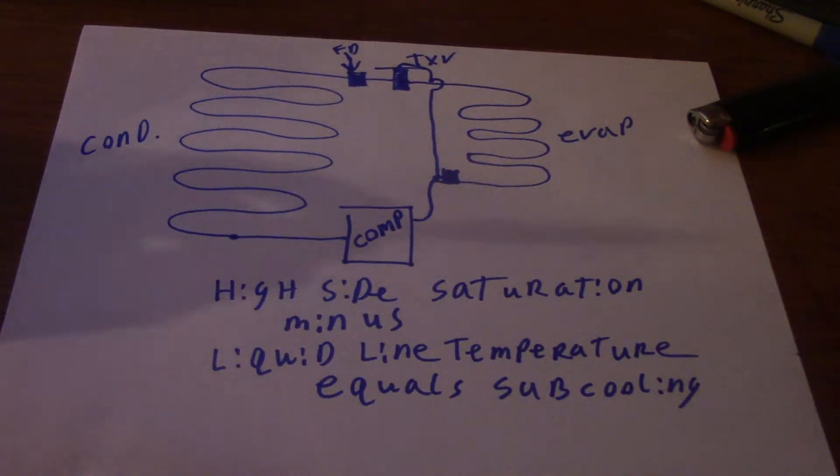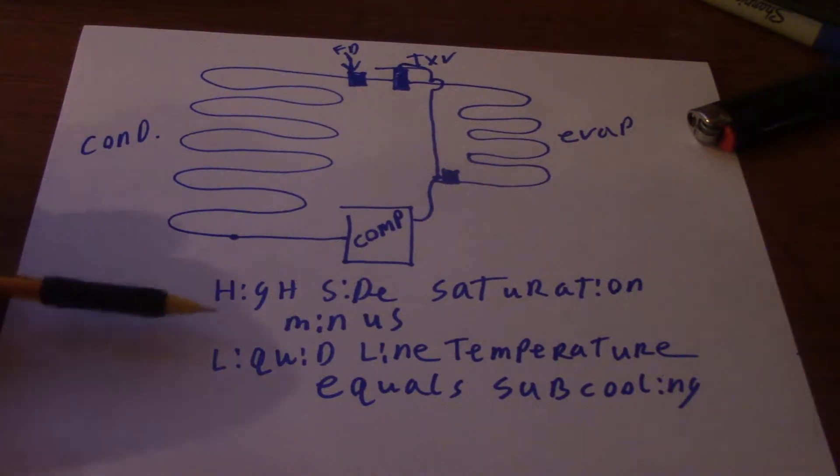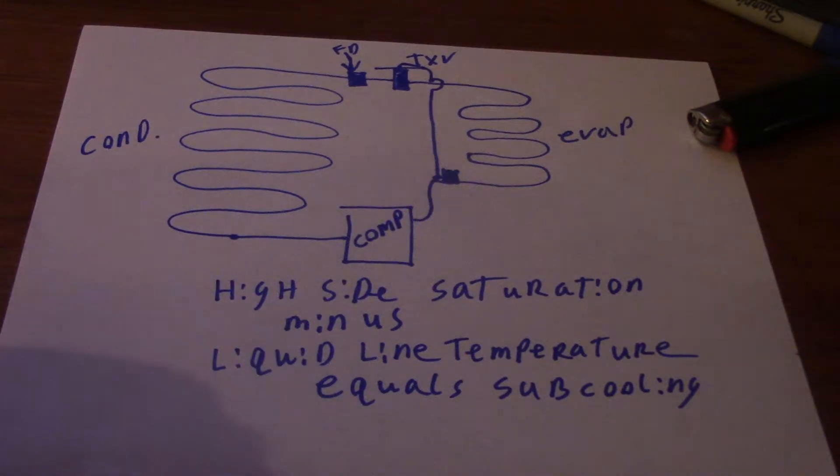You have to remember to follow the formula. It's going to be high side saturation minus liquid line temperature to calculate subcooling. That is the formula. It is specific you have to have there.